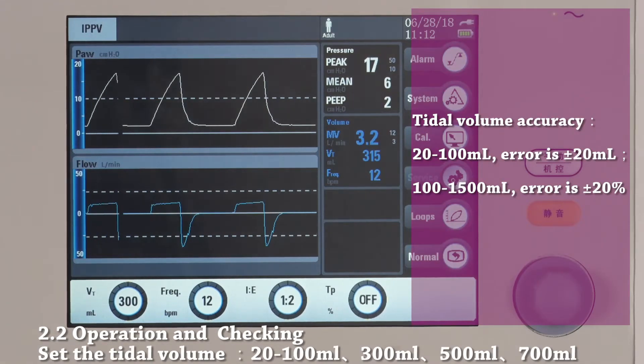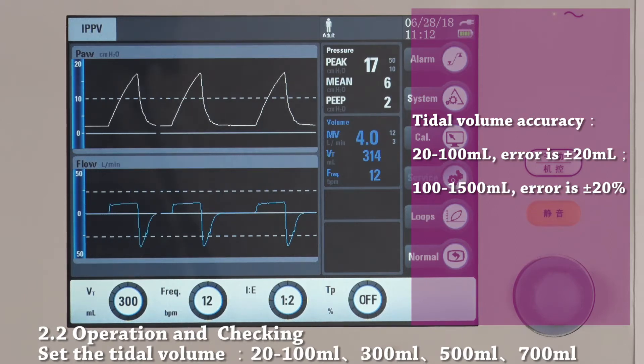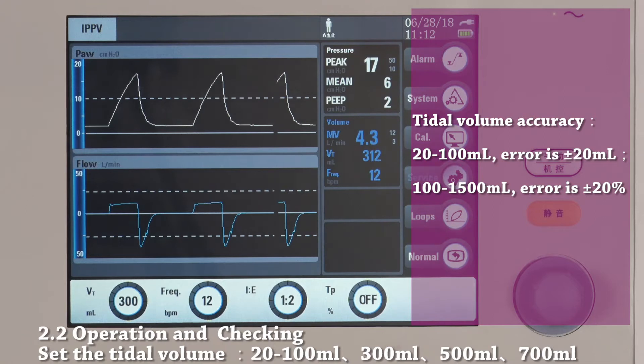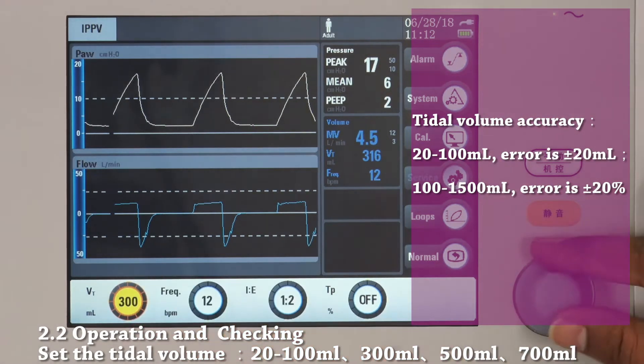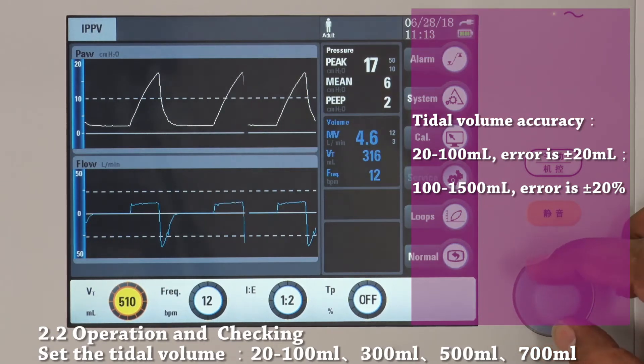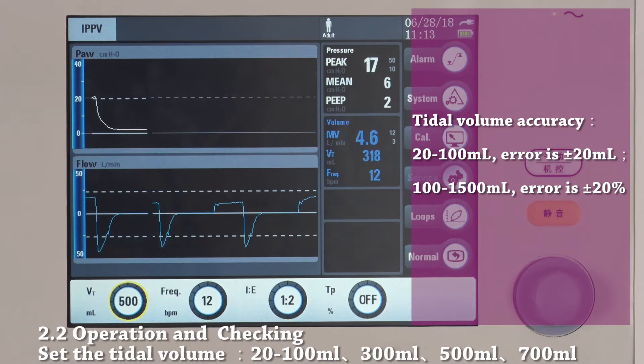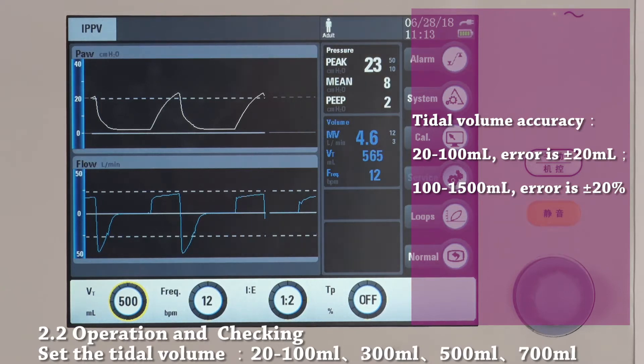This part is to show you how to check the tidal volume accuracy. In child mode, for tidal volume range from 20 to 100 ml, the error is plus or minus 20 ml. For adult patient type and for the tidal volume range between 100 and 1500 ml, the error is plus or minus 20%. We will demonstrate for adult patient type with a tidal volume of 500 ml. We will set breathing frequency to 12 and inspiration-expiration ratio 1 to 2. Comparing the set tidal volume and actual tidal volume, we can see that this value is between 400 and 600 ml, which is inside the error range.